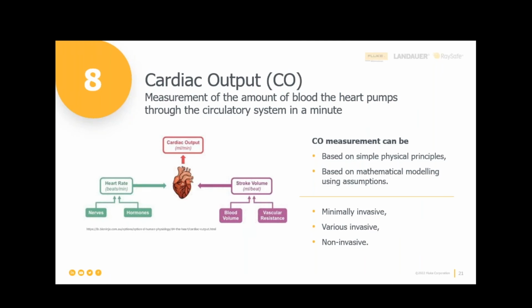Cardiac output, we can simulate, but again, it's based on what the monitor is looking for, and then we give it an electronic simulation that it can respond to, and we're looking for specific responses. These are called out by the manufacturer in the brand and model specific test procedure. There are specific accessories that you need in order to connect your simulator, including ours, to the patient monitor for cardiac output. And it is based on the thermal dilution type of cardiac output, not any other way of measuring cardiac output, because there are two or three other ways you can get an assessment, but those sensors are very expensive and are less typically used or found.